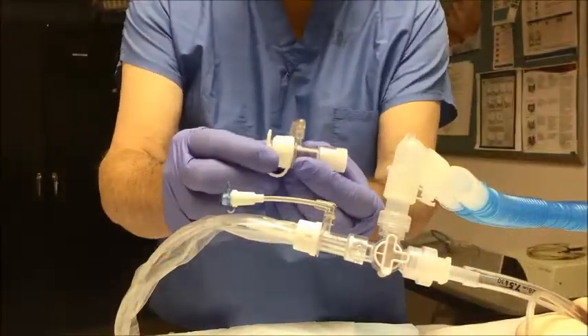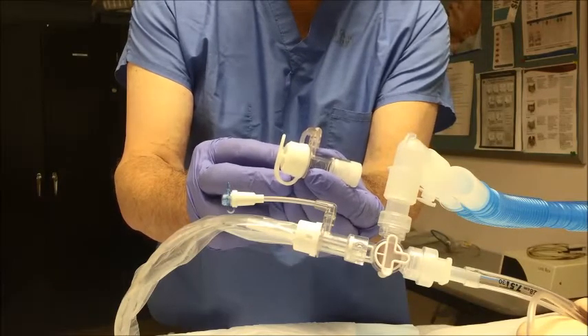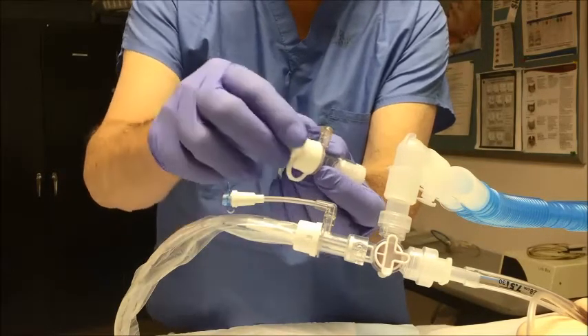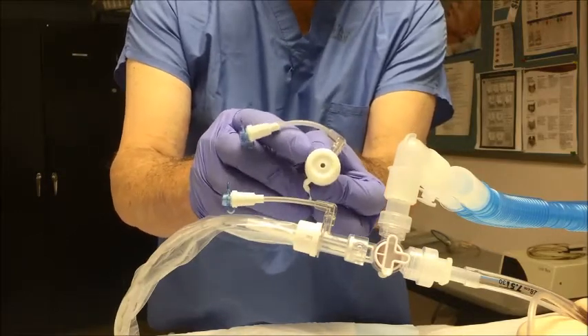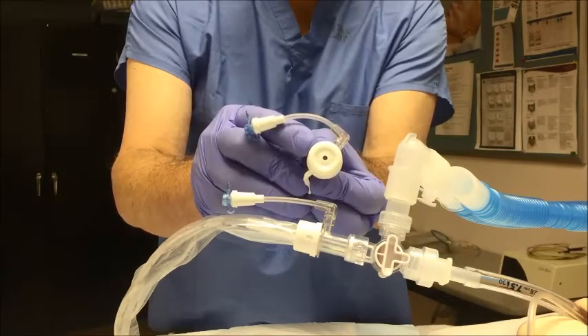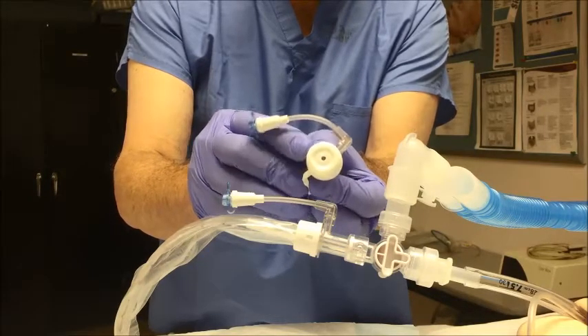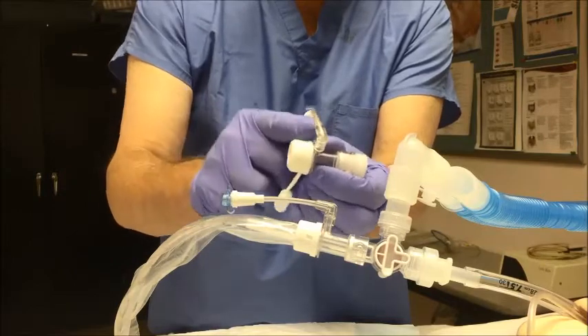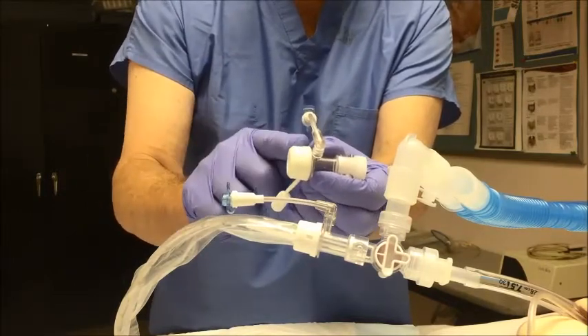Intubated patients sometimes require instrumentation of their airways, either for bronchoalveolar lavage or bronchoscopy while in the ICU. This is the endOclear bronchoscopy adapter that works with the endOclear Liberator airway maintenance system. The bronchoscopy adapter is also a modular component of the system. It has a flexible diaphragm that accommodates size instruments between 3 and 8 millimeters, and once the instrument is inserted, it is air tight to 40 centimeters of water pressure.